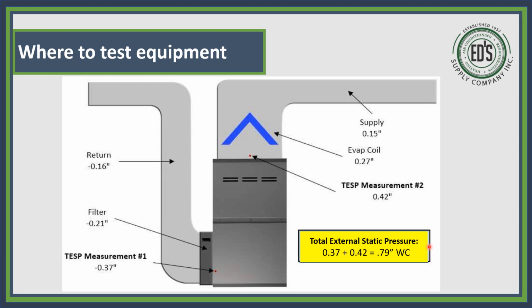So if you look at your chart in your install manual, it would tell you to go to whatever size model that return is, or that unit furnace is, and find out what speed tap you're on. Let's say we're checking this in AC. If we're checking AC, this coil is going to be wet. It's going to have a little bit more resistance on a wet coil than on a dry coil, so you want to keep that in mind. But if we're testing it here, you're not catching that. You're not getting this wet coil. You have to test it up here on this side to get that wet coil. So you've got to understand that.